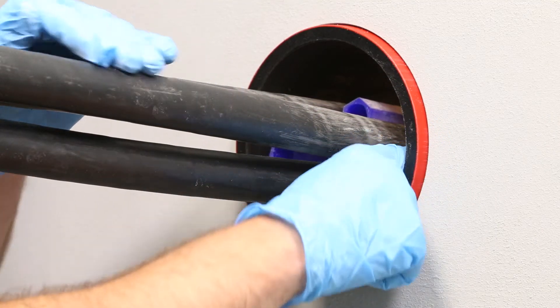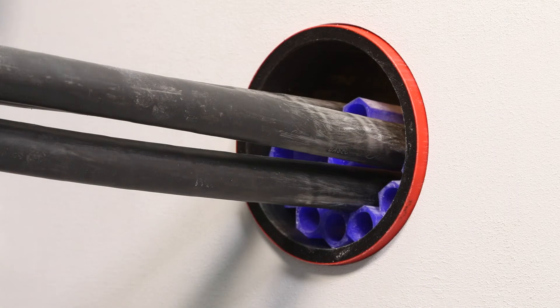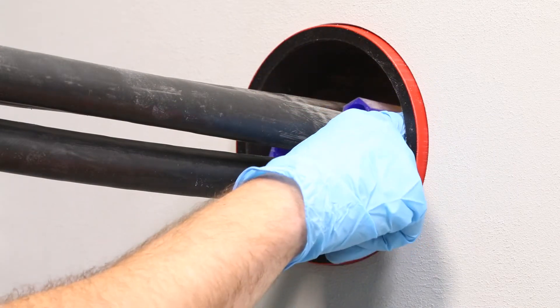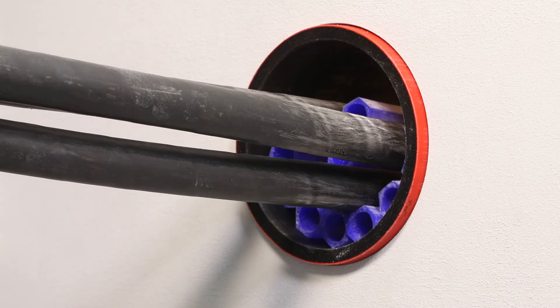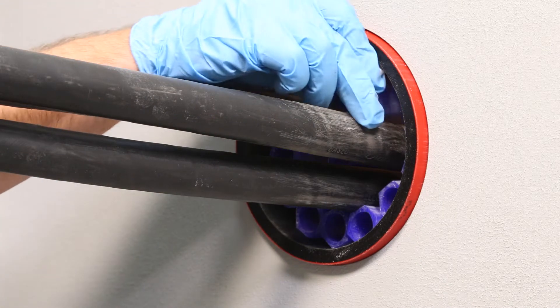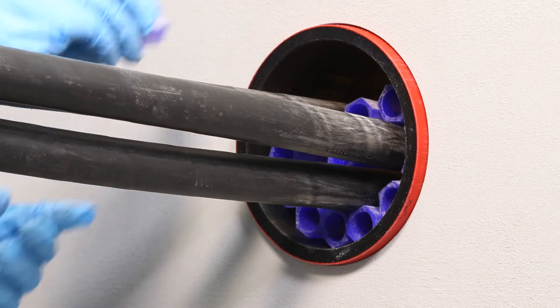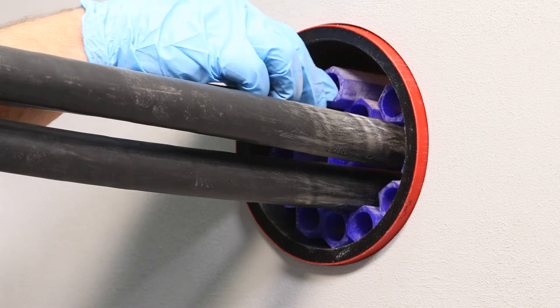Using the backing hexagonal tubes, insert these around and between the cables, ensuring you obtain the 5mm spacing. A neat installation is with the flat sides of the hexagonal tubes coming together cleanly. The tubes can also be cut and wrapped around the cable if required.